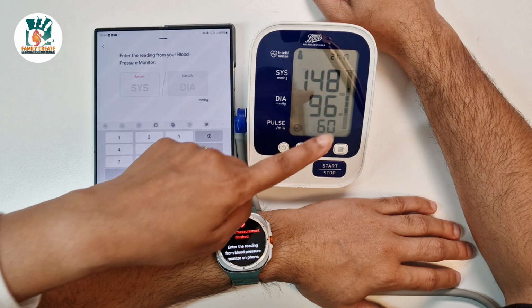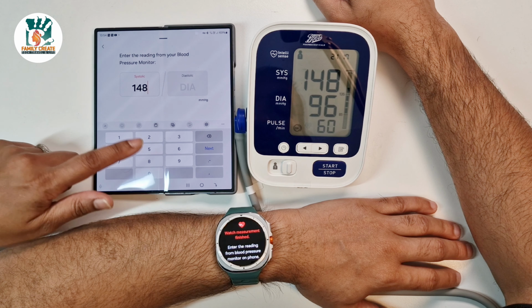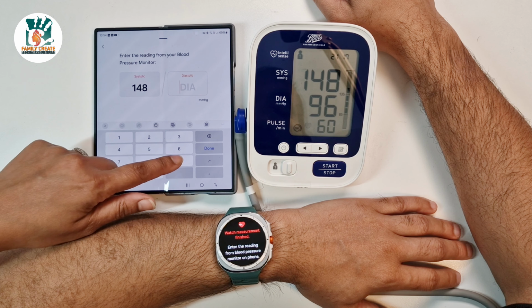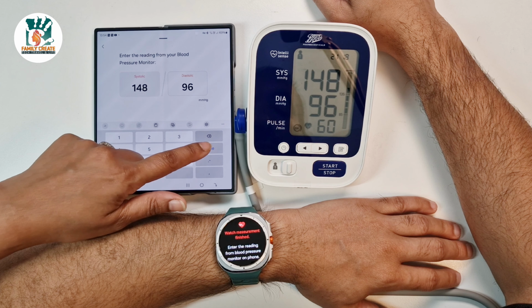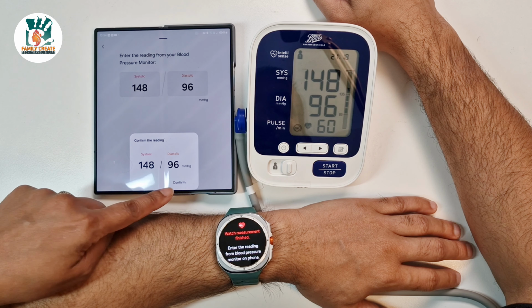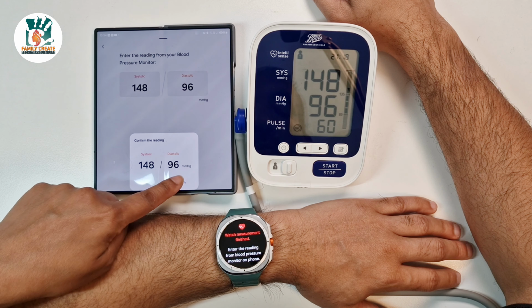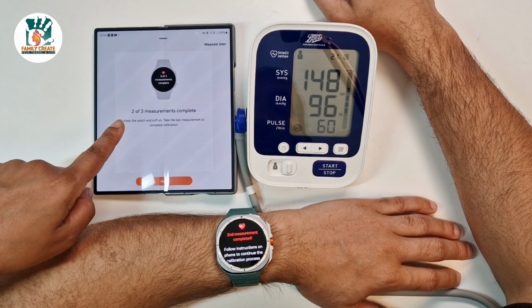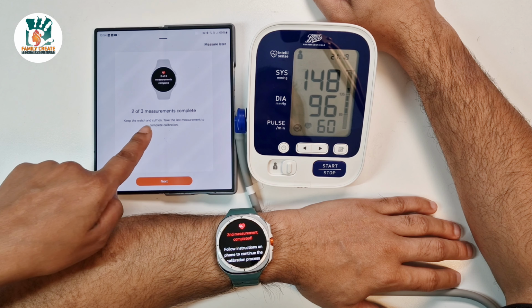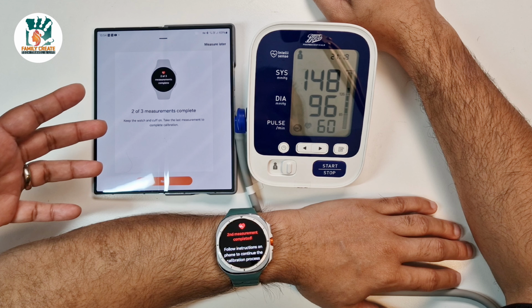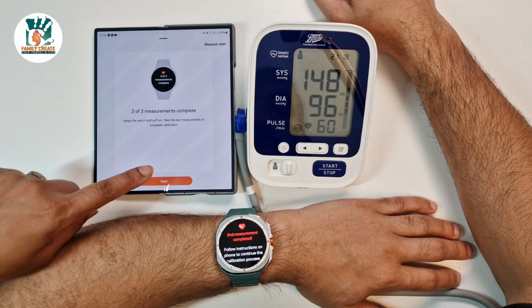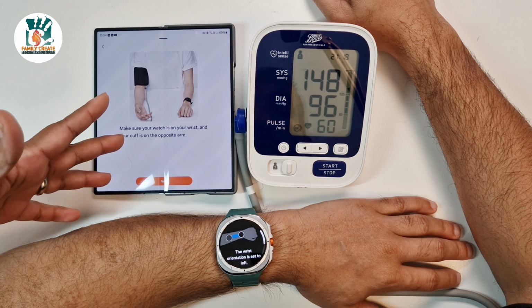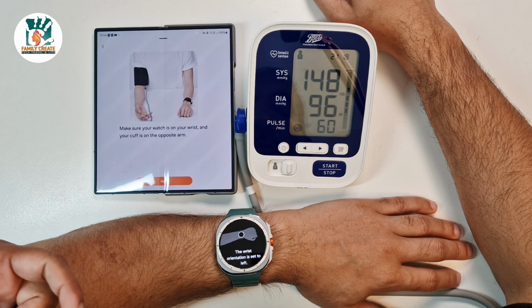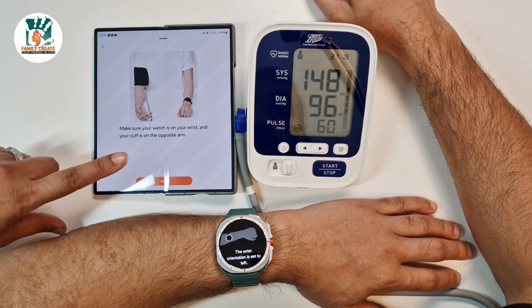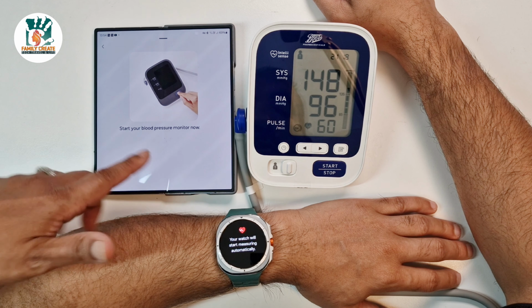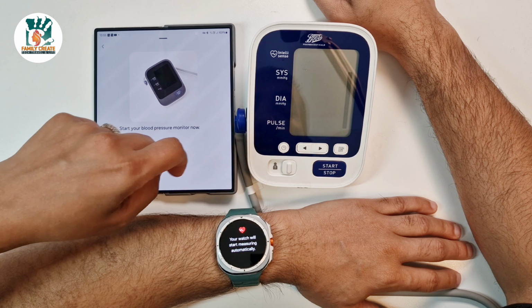So the second reading is 148 over 96, and done. This is the reading we've entered, and it's asking to confirm. We're just going to confirm. Second of the third measurement complete. Keep the watch and cuff on. Again, it's asking to repeat the calibration. So we're going to say next, and then again the same instruction. Watch on one hand and opposite, you should have the arm cuff. Next, so start the blood pressure again. We do the reading again.